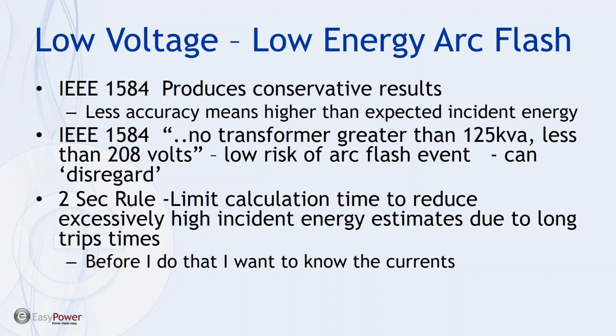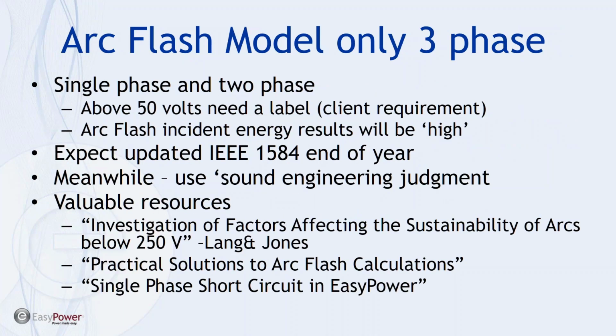It also talks about a 2-second rule through which you can limit the calculation time to reduce the excessively high incident energy due to long trip times. Well, before I do either one of those, I really want to know what the currents are. And to Saeed's question, EasyPower currently only models 3-phase systems.